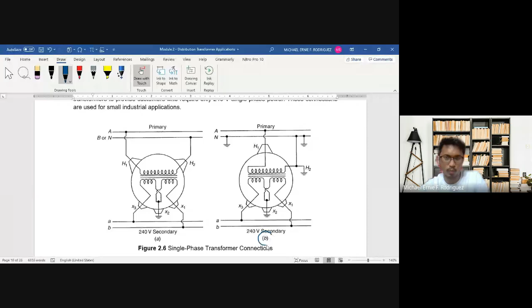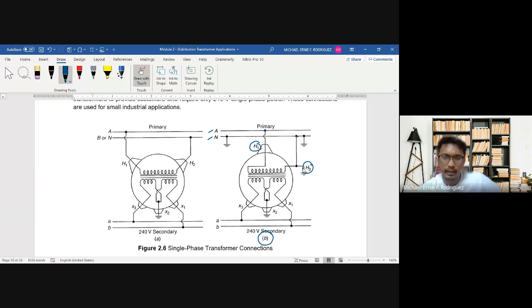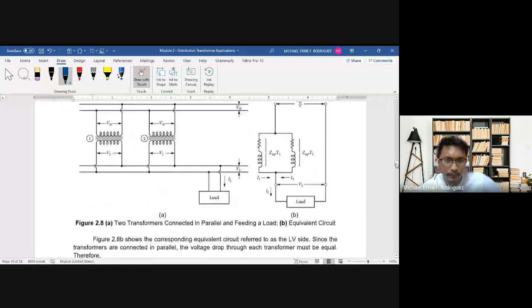So on the primary line, we have phase A and the neutral. We have A here, tapped to your H1, that's A, you can see it there. And then our H2 is grounded, connected to the neutral - connected to the neutral and then grounded. And then we have here...